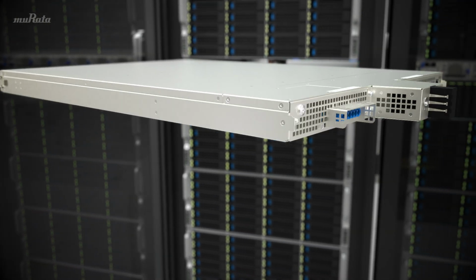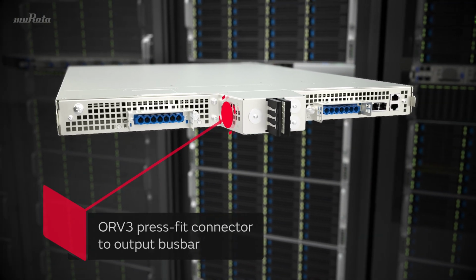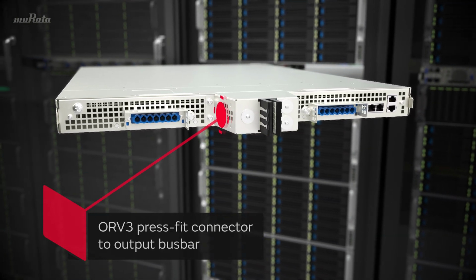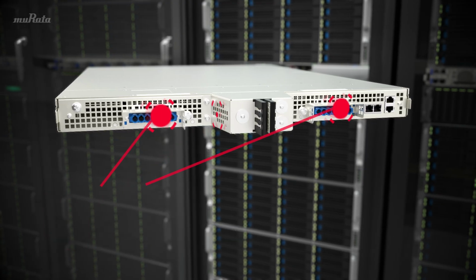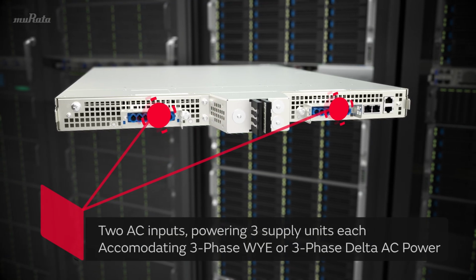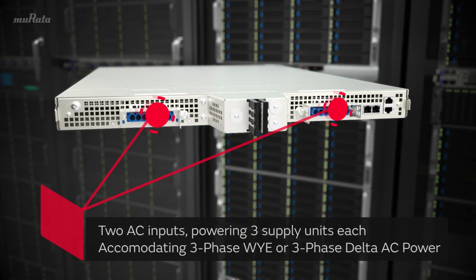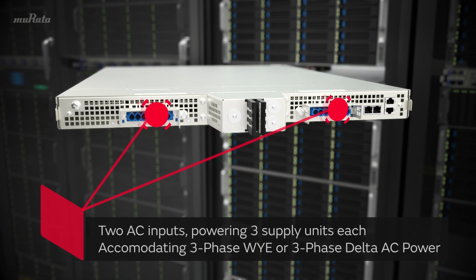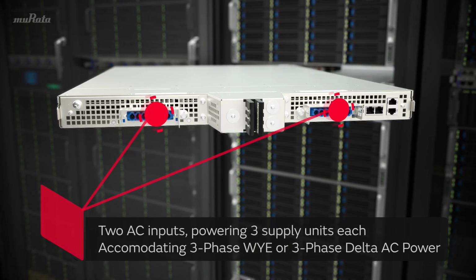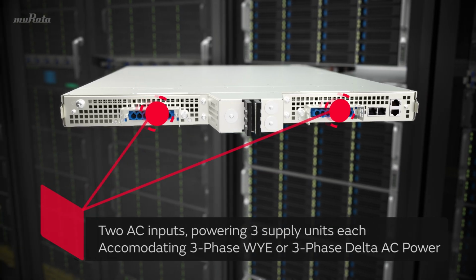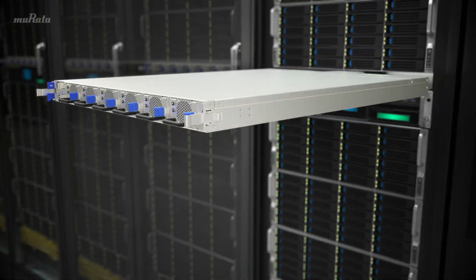The shelf is configured with a press-fit DC output connector that contacts the Open Rack V3 busbar. Two AC input connectors are provided for AC redundancy, configured to power a group of 3 power supply units each. They can accommodate either 3-phase WYE or 3-phase Delta AC power.